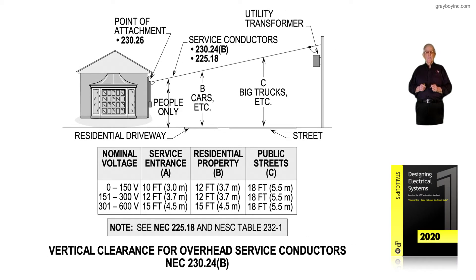This illustration deals with vertical clearance for overhead service drops in accordance with NEC 230.24B — as in 'boy.' Notice the information in the boxed-in area: there is a column for nominal voltage, a column for service entrance clearances, a column for residential property, and a column addressing public streets.